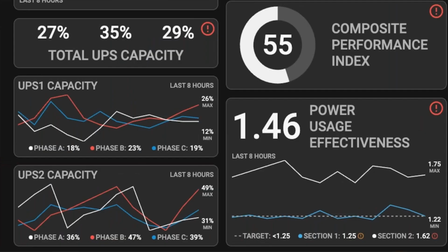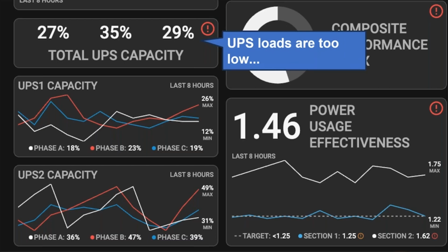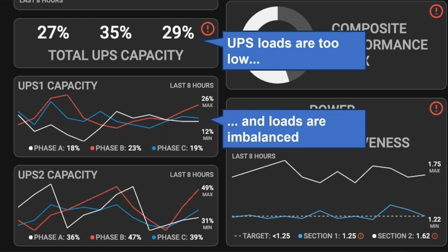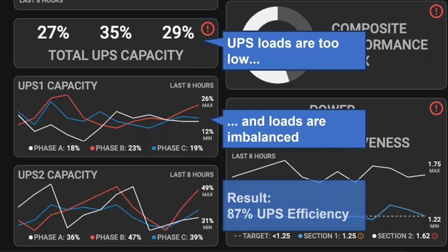Okay, and looking at my UPS capacity, I see two things. I see that my total load is around 30%, 31%. That's quite low, and a UPS is never efficient when it is so low. The other thing I see is that there is an imbalance. Between phase 1, 2, and 3, there are differences, and differences in phase balance will result in zero currents, and zero current is 100% lost. So two things are wrong: balance and load. And if I look at the total UPS part, including my cabling, my UPS efficiency is at 87%, which is not very good, I think.